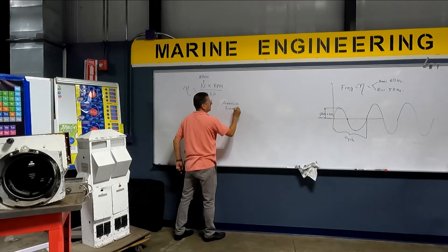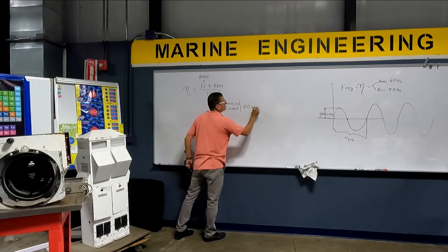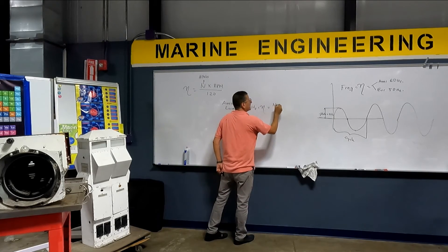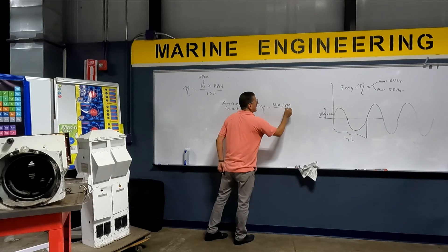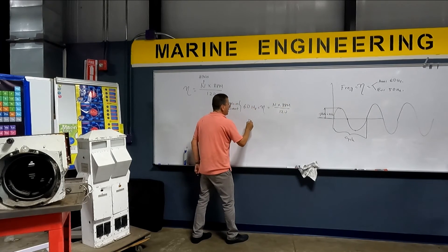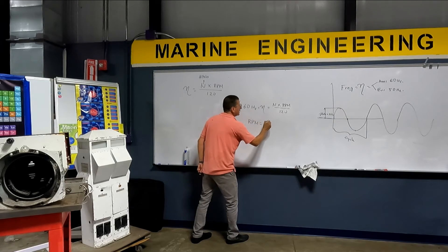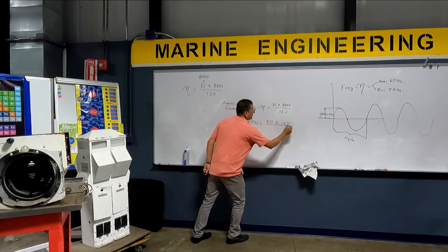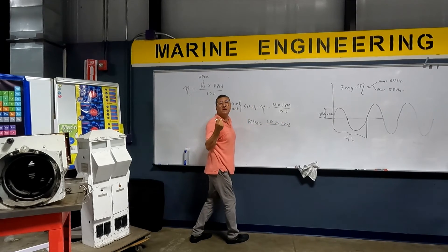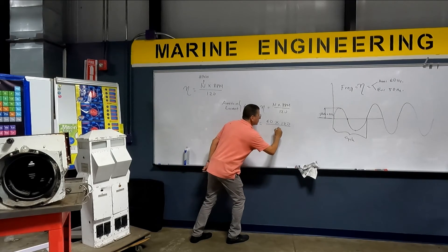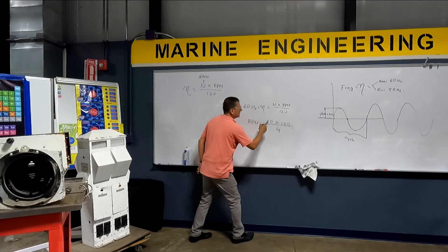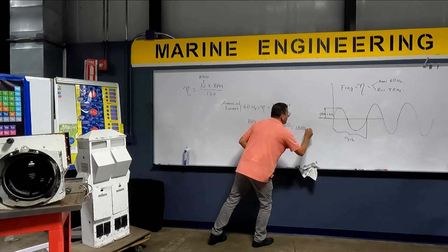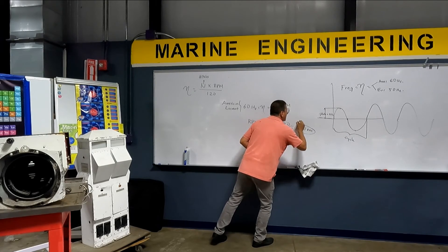American current is 60 hertz. The formula is: frequency = (number of poles × RPMs) / 120. To find RPMs: RPMs = (60 × 120) / number of poles. A typical generator has four poles. So: 60 times 120 divided by 4 equals 1800 RPMs. American generators run at 1800 RPMs. Don't forget — this is for American power.